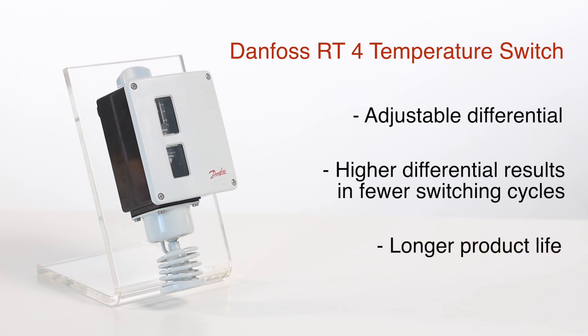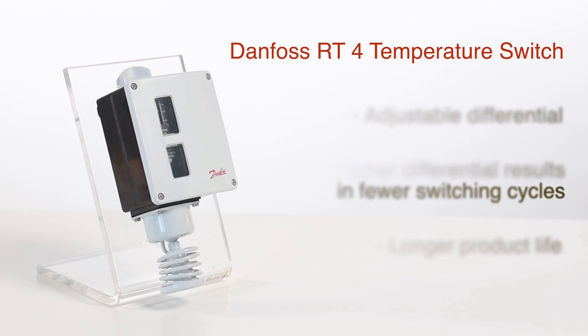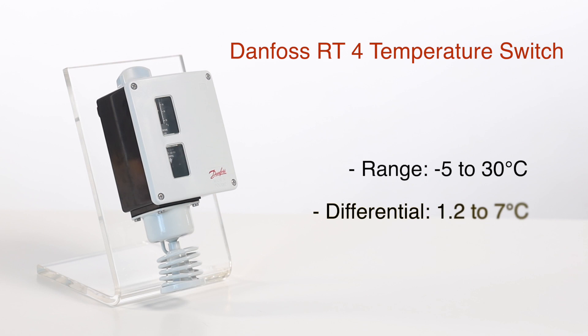In our example, we'll demonstrate how to set up a Danfoss temperature switch for rising temperature applications. In this case, we have an RT4 with a measuring range from -5 to 30 degrees Celsius and a differential from 1.2 to 7 degrees Celsius.